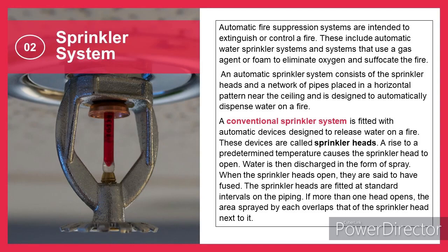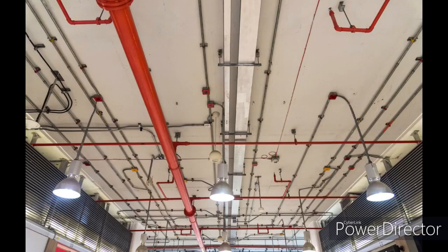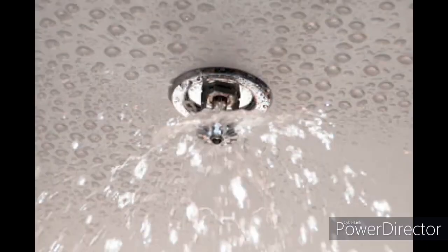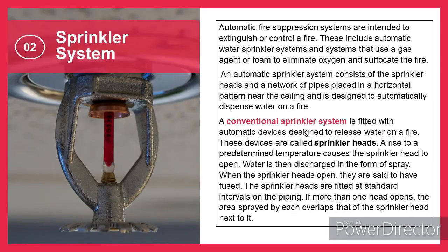Automatic fire suppression systems are intended to extinguish or control a fire. These include automatic water sprinkler systems and systems that use a gas agent or foam to eliminate oxygen and suffocate the fire. An automatic sprinkler system consists of the sprinkler heads and a network of pipes placed in a horizontal pattern near the ceiling and is designed to automatically dispense water on a fire. A conventional sprinkler system is fitted with automatic devices designed to release water on a fire. These devices are called sprinkler heads.